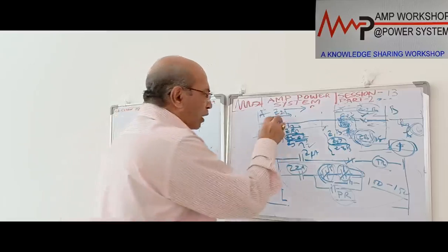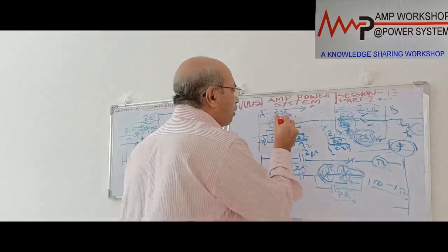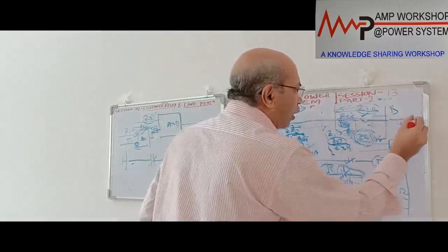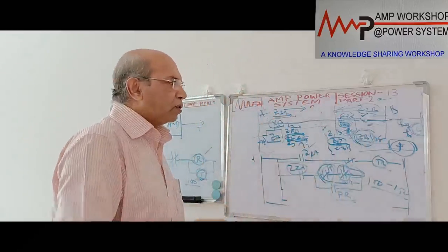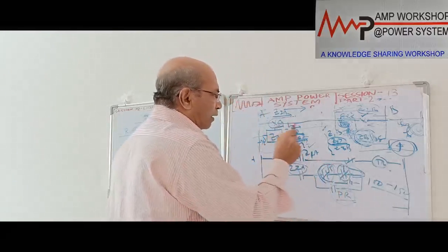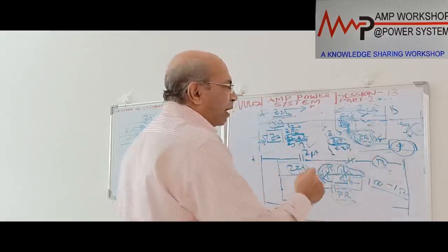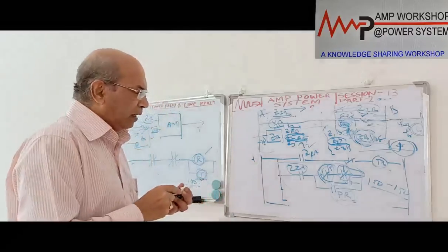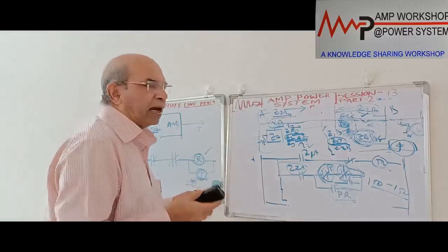Okay, because when the Z2 element is operating over here, it indicates what? It indicates that the fault could be inside or the fault could be in the 120% outside. In both cases, it can be operated. So that's why, when the channel failed, if the fault is internal it will be cleared, but if the fault is outside, this line will also be tripped unnecessarily. The risk is there. This is your permissive, your directional unblocking scheme.